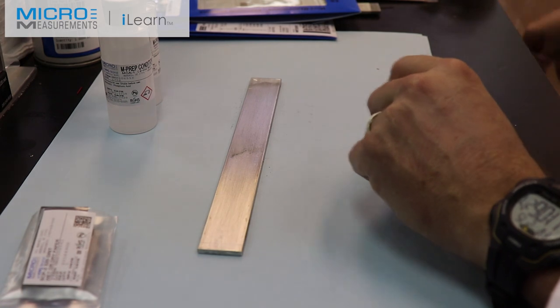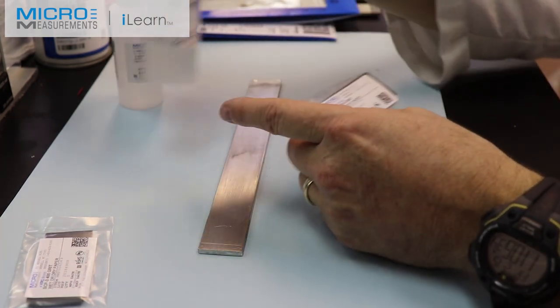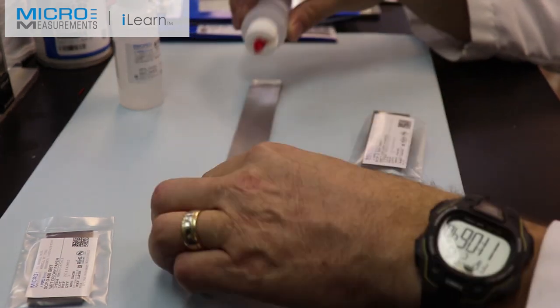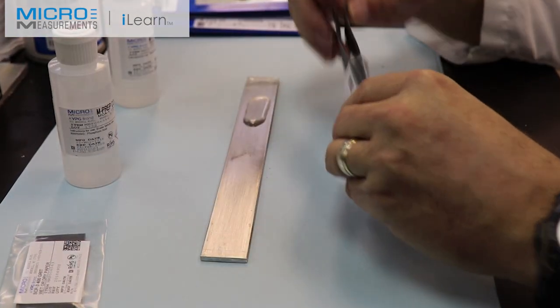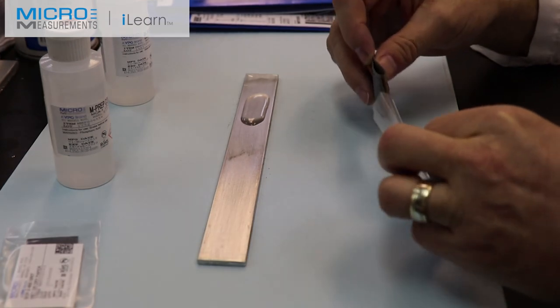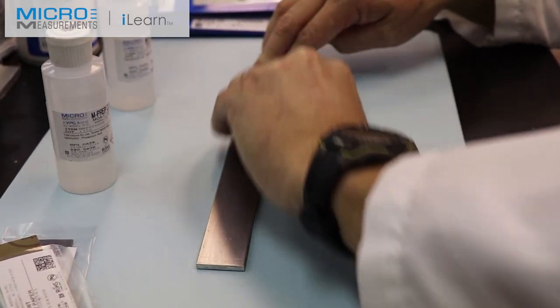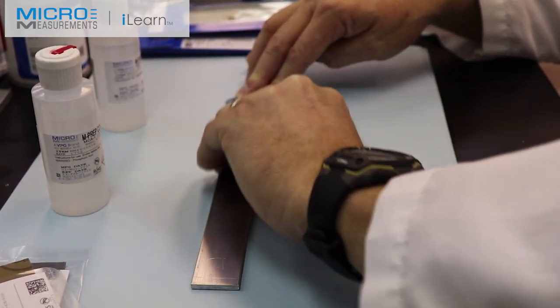Once I've done that, I'll discard that piece. The very next step is going to be a wet abrade. With the wet abrade, I'm going to use 320 grit paper combined with the red tip bottle — the M-Prep Conditioner. I'll take the conditioner, put a few drops on the surface, close it back up, take another piece of silicon carbide paper, fold it, and abrade back and forth about eight to ten strokes. What you're trying to do is lift off contamination and introduce a uniform texture — you want some texture for the adhesive to bite to.